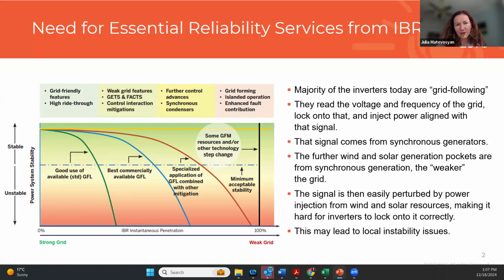You'll hear the term weak grid, meaning this part of the grid is far away from synchronous generation. The signal that inverter-based resources need to synchronize with the rest of the grid is easily perturbed by injection from these same inverter-based resources themselves, making it hard for them to synchronize to the grid. This may lead to local instability issues. So basically, the term grid following comes from the fact that inverter-based resources need a strong voltage signal from the grid to synchronize to it.